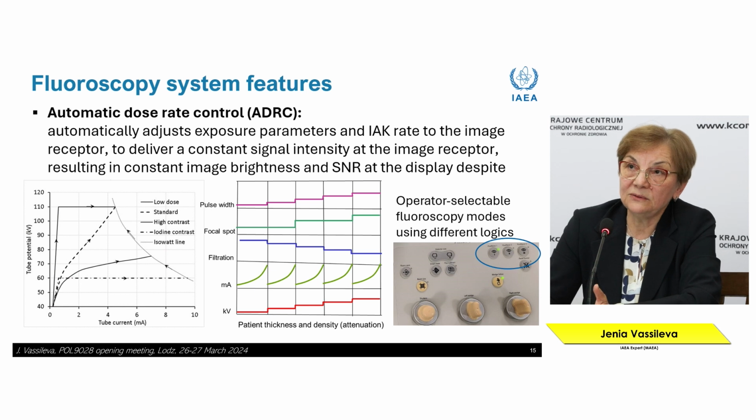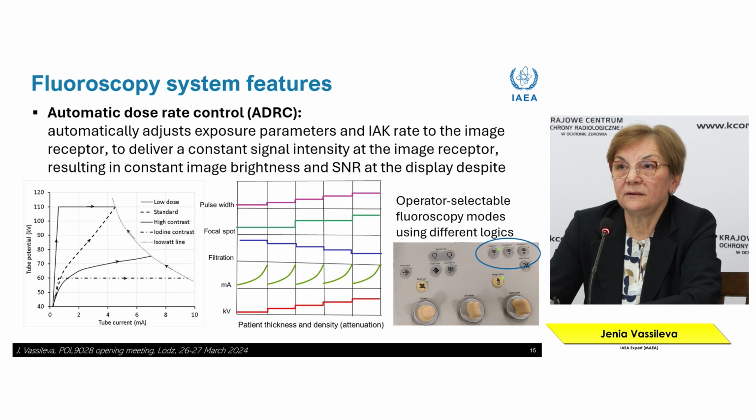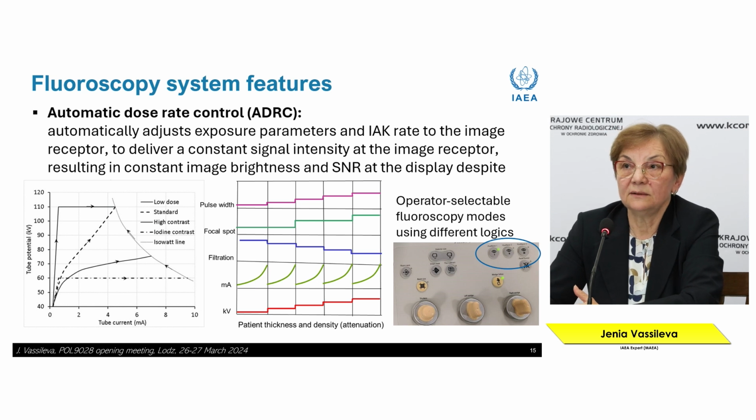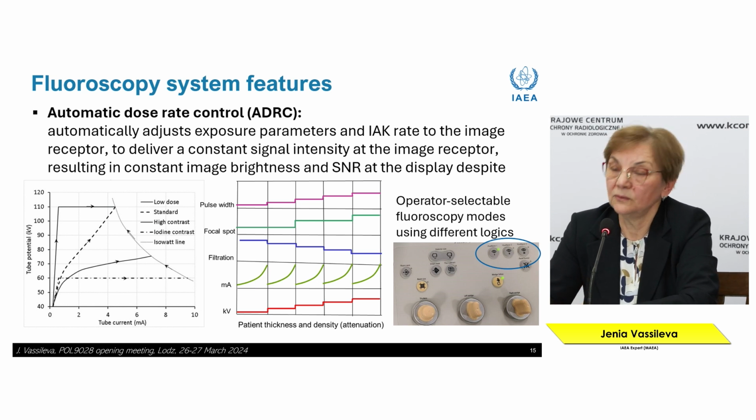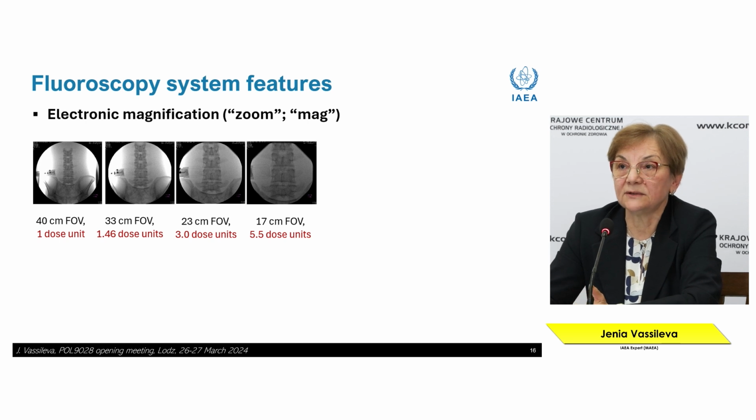And for the operators, it's very important to know the control panel, because there are operator-selectable fluoroscopy modes that use different logics, and the operator, either interventionalist or technologist, should know which of these modes is linked to what kind of exposure, and of course image quality, because these functionalities are there to be used for the best result of the procedure.